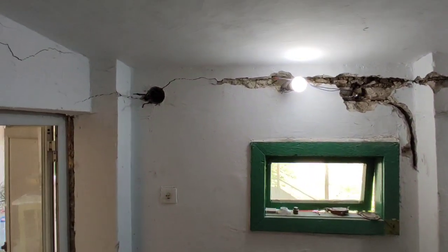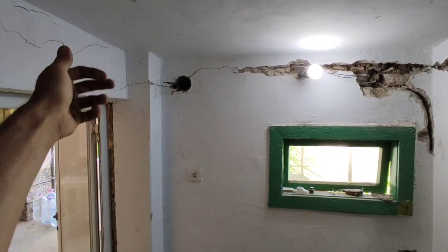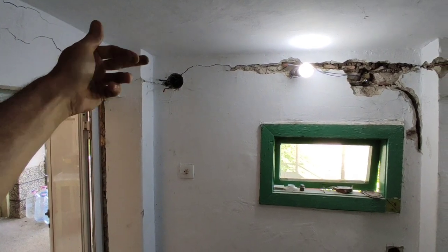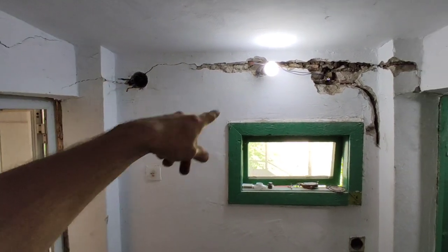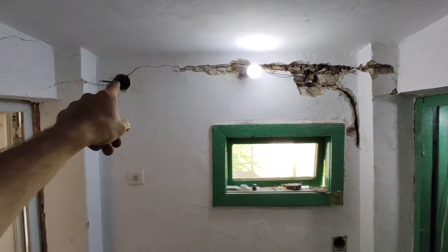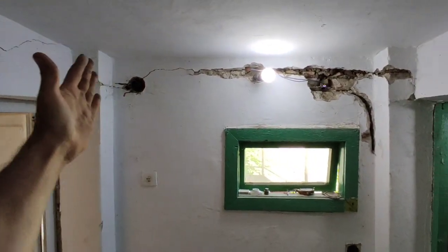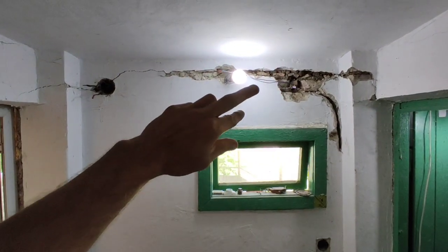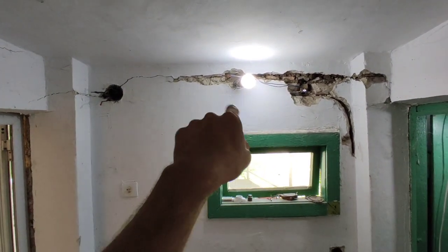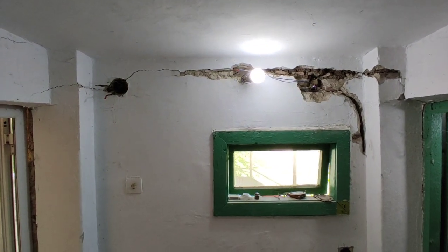So Dad's figured out what the problem with the electrics was, and it turns out where the junction box is on the outside, the live and the neutral have been switched, which meant even though you turn the light off, the actual housing was still live. And although it goes outside and comes back in, everything past the door was basically oppositely installed, which is pretty dangerous. If you unscrew the bulb and you put your finger in, obviously it's going to be live, so it's not very safe.